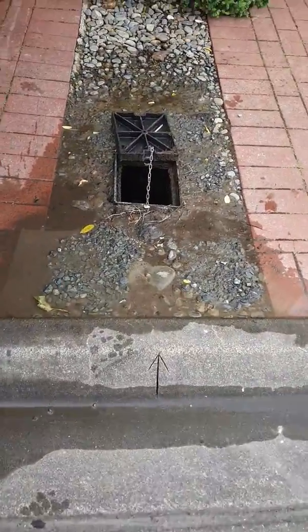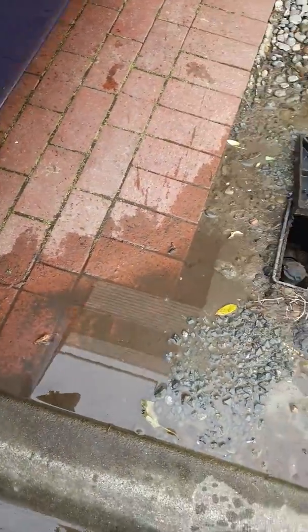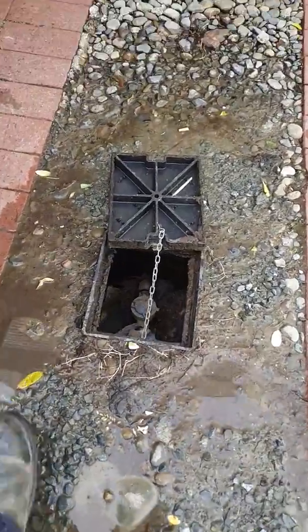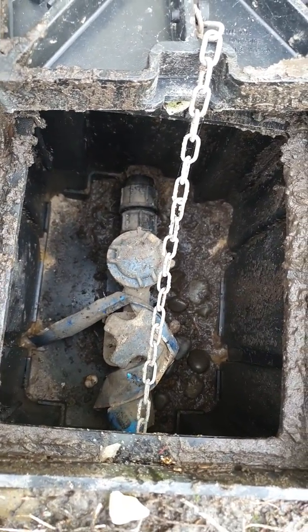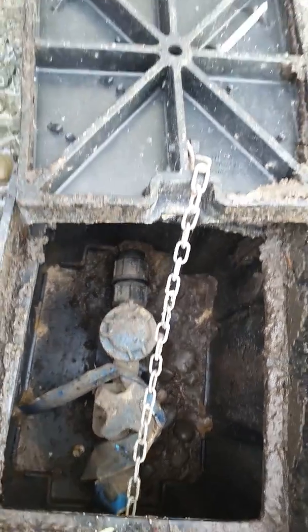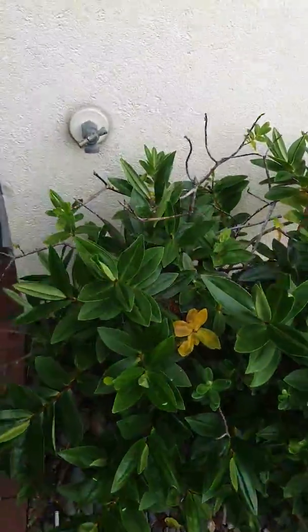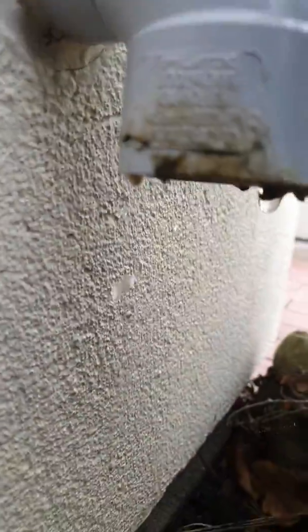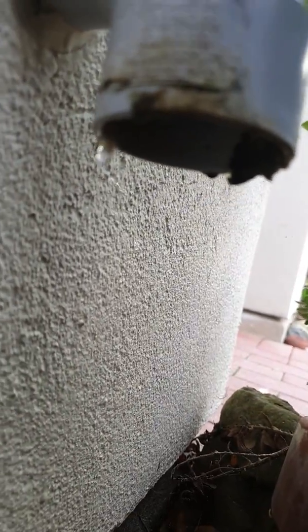Okay, here we are. I've noticed that there's water on the outside — for the amount of water that was here and around, I lifted up the junction box expecting it to be full of water, as you can see it's not. But if we go up to here, you'll see there's a pipe that's leaking continuously. You can see how it's quite black around there.